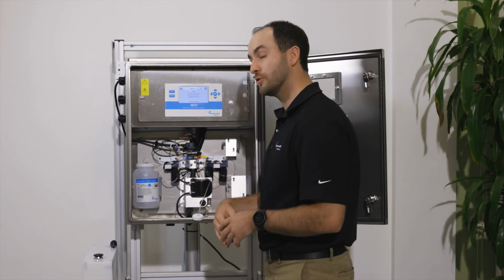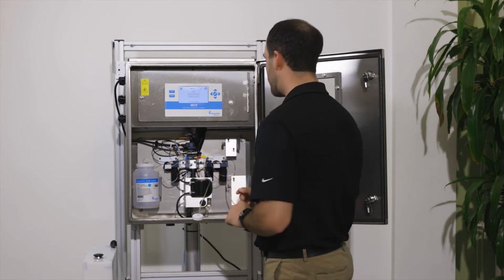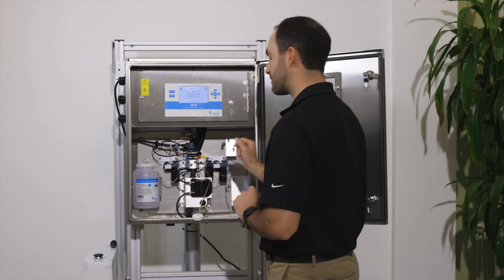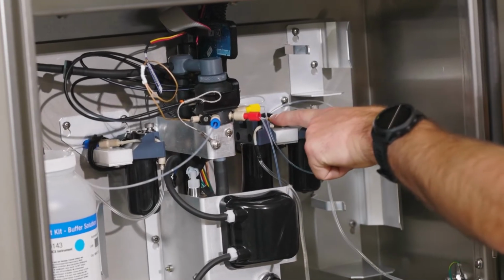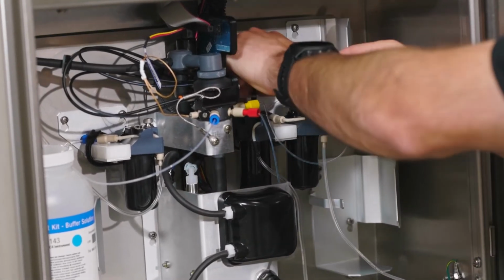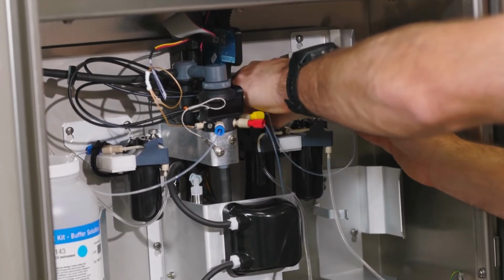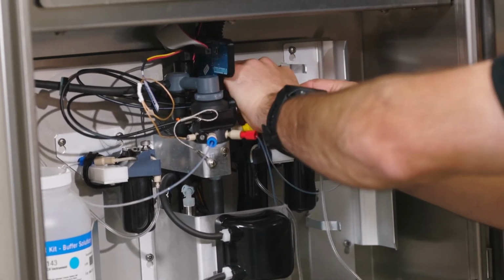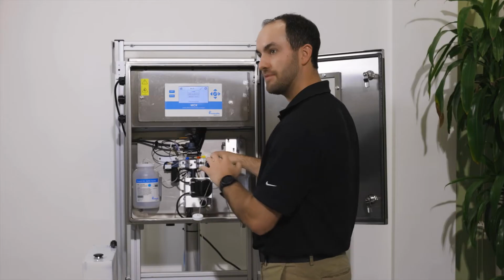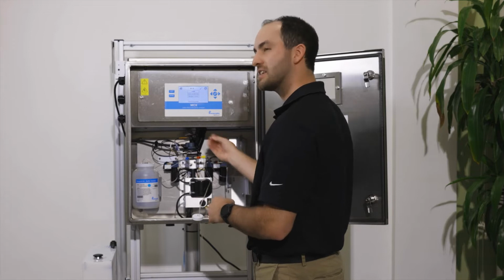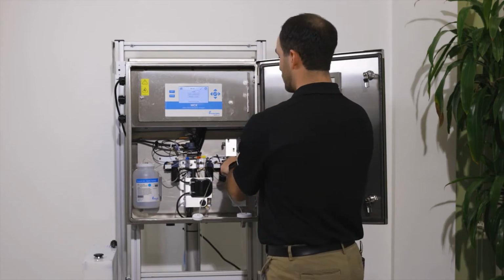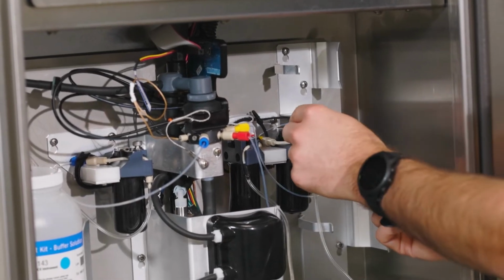After the bottles are removed, we're going to want to go ahead and get all of our tubing off to free up the reagent pump. We'll start by taking off the black Velcro. I like to loosen it and leave it there since you're going to need to put it back on, and it is tough to get back in there. We'll take the pin off of the reagent pump that we're changing.